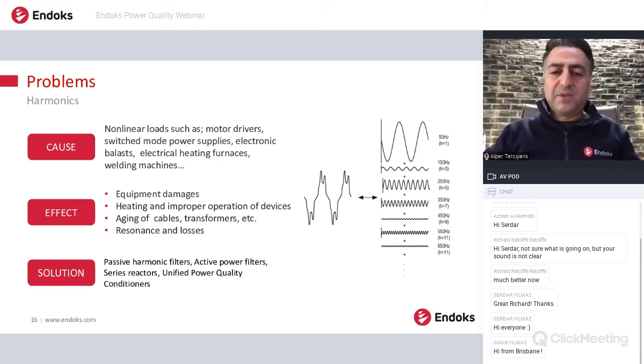You see, for example, the waveform on this slide. There's a distorted waveform, and if we do an FFT on this waveform, we get the fundamental and harmonics. So we need to avoid harmonics because they create additional losses. They create additional stress on equipment, and they can also trigger resonance problems in the power system. You know the resonance issue actually. Let's say there is a system and it has a resonance frequency, for example, 250 hertz. If you inject 250 hertz current into the system, and its parallel resonance frequency is 250 hertz, then even a very, very small injected current creates bigger and bigger currents and voltage on the system.